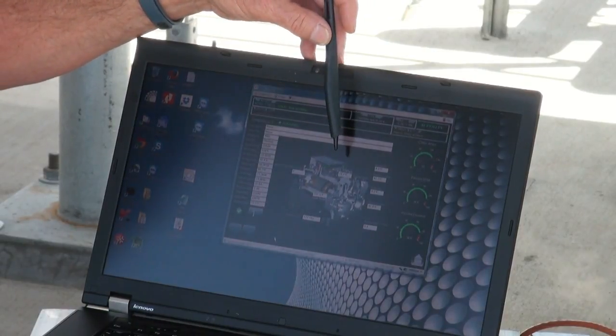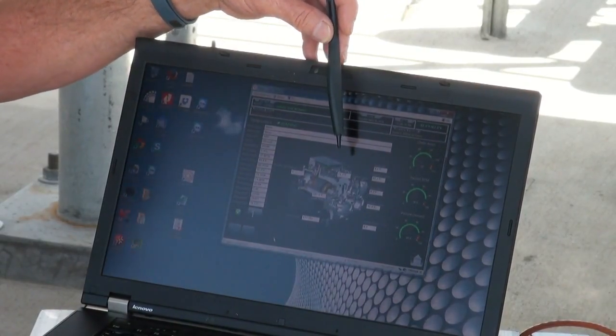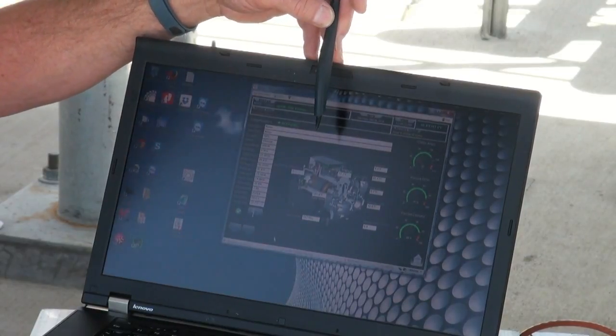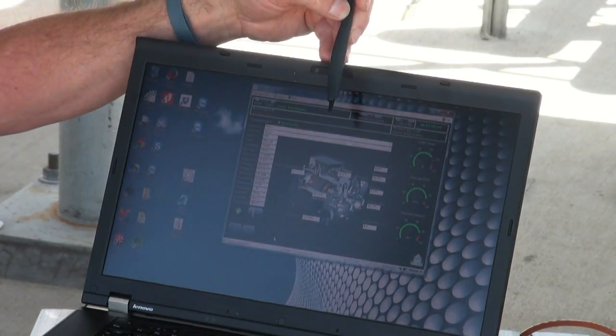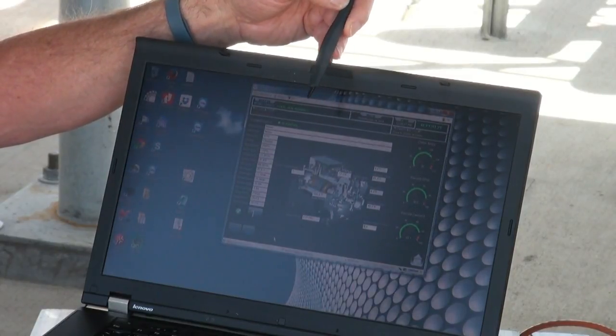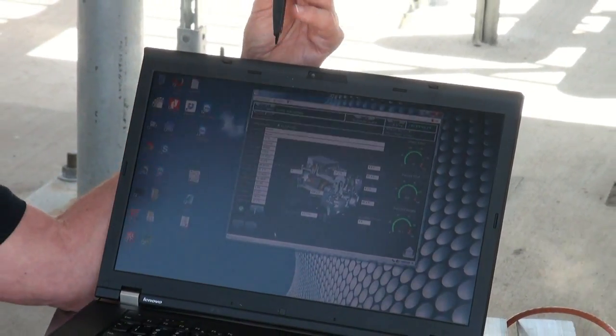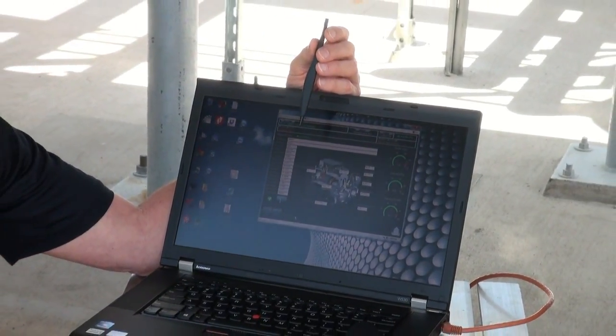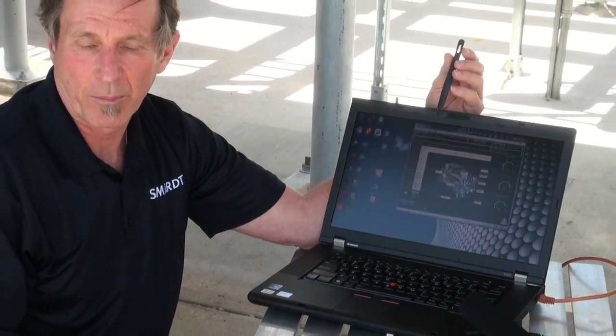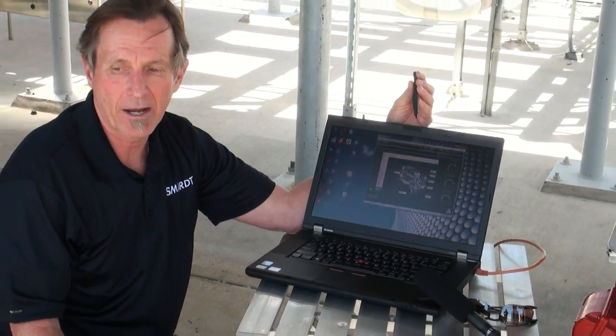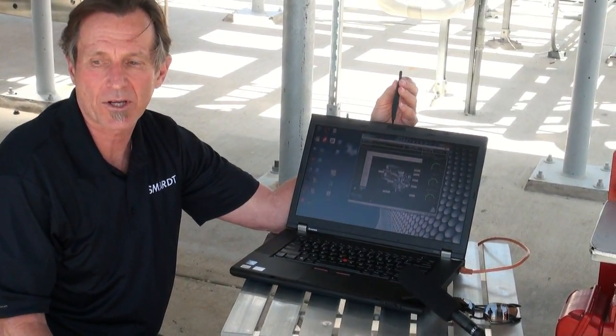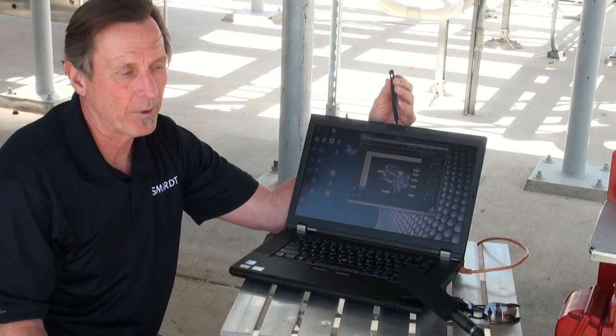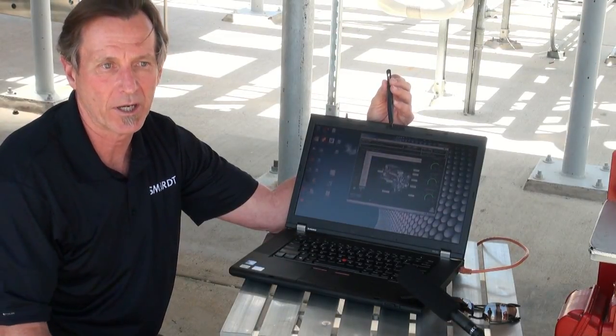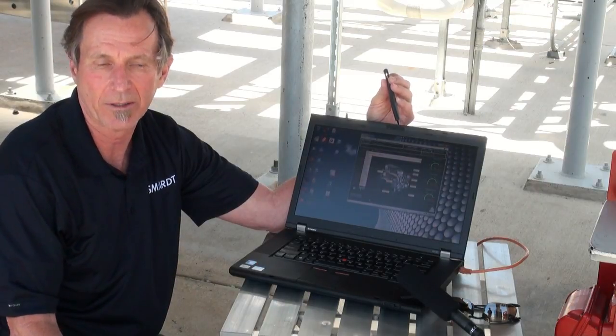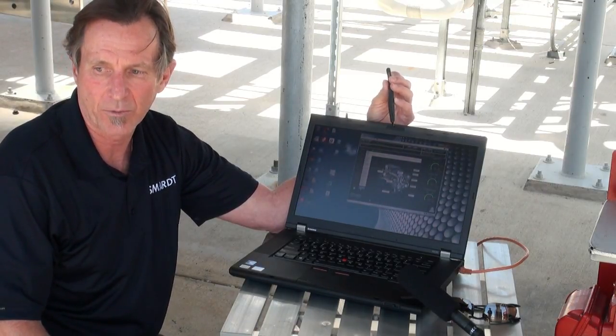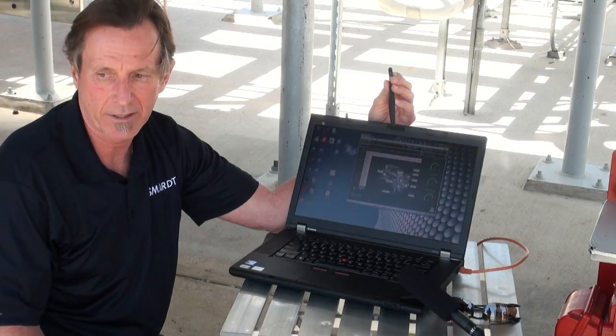Our critical fault on the inverter is 175 degrees. That's the point we'll trip. Actually, we get into an alarm first. There's an alarm setting and a critical fault setting. The alarm setting is just the point where you're getting close to your critical fault. So the compressor will react by slowing down. It'll try to slow down, try to stay online. But if it can't, and you continue to increase the temperature to the critical fault limit, then it'll shut down and do a reset. It'll automatically reset at that point.